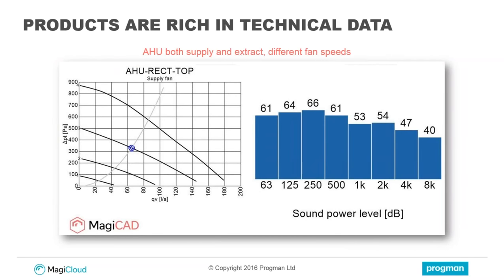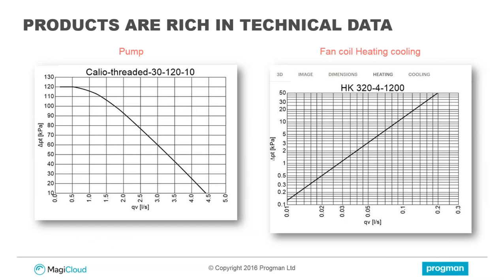When you look at specific product types, you can see the incredible amount of data available because the information is coming directly from the manufacturers. For example, a supply fan with supply and extract information — we have sound power level data, which is incredibly powerful, because you can run sound calculations inside MagiCAD, which is a rather unique feature. Inside MagiCloud, you can also move the operational point around, so you can actually see how a product would operate before you even take it into your project. Then when you take it into the project, you're able to run additional calculations and get this real accurate information to use in your design work.